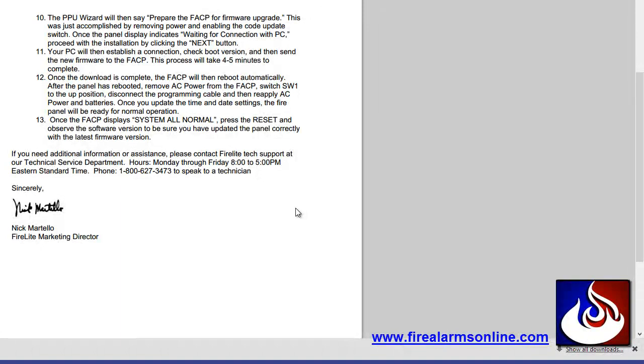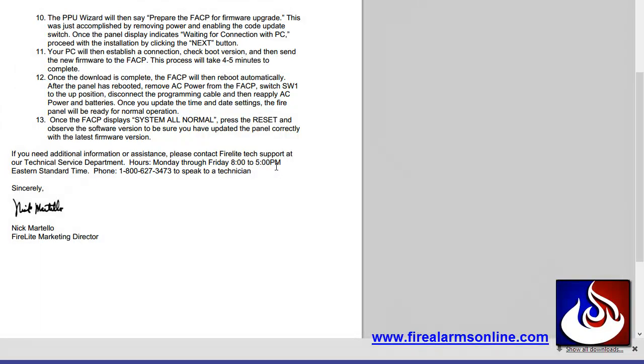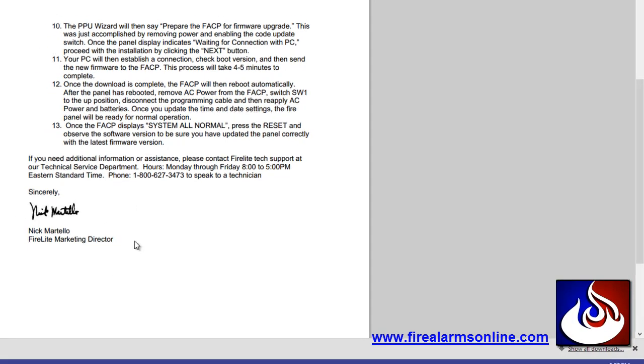it says once the download is complete, the FACP will reboot automatically. After it has rebooted, remove the AC power and DC power from the panel once again and put the SW1 switch back into the up position. Disconnect your programming cable and reapply power, the AC power and batteries. Once you've updated time and date settings, the panel will be ready for normal operation. You'll know it's good when the panel says all normal and you can simply press the reset button to check out what version is currently in the panel and make sure that your firmware update took. So it's pretty much as easy as that.